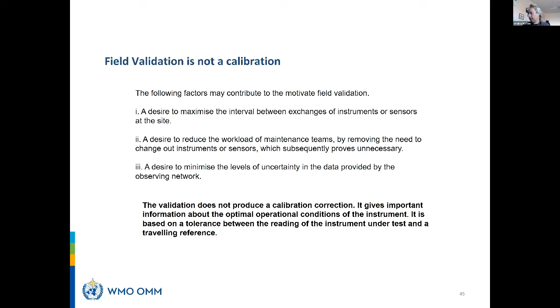But finally, the validation does not produce any calibration curve. The validation just tells you whether you are within limits. What you obtain is a tolerance: okay, my instrument is within my tolerance limits. The calibration, not the validation, is the only way to establish the traceability of the instrument, as we said, by the definition of traceability.